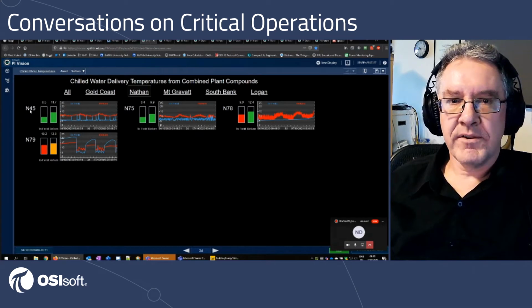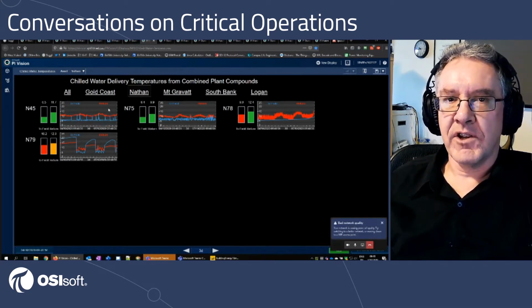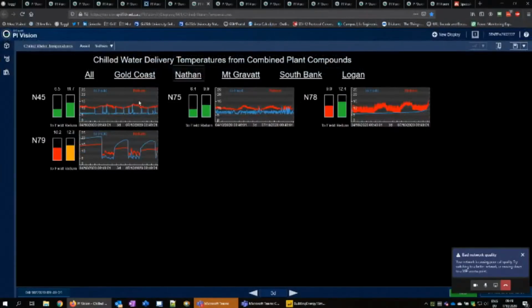If we go back to chillers, specifically to this chiller house, we're about to replace the chiller house. We have nearly 5 years of data for this chiller house. A classic chiller house setup is you put in one low load chiller and multiple larger chillers, because that's accepted knowledge, that's just what you do. So our engineering team analysed all of our data and looked at the COPs for our chillers.